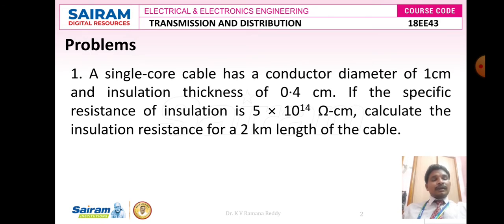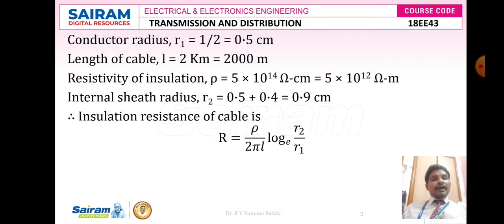The resistivity of the insulation, that is the specific resistance, is 5 × 10^14 ohm-centimeter. Converting to ohm-meters, we multiply by 10^-2, giving 5 × 10^12 ohm-meter. Now we need to calculate one more radius, that is the insulation radius.